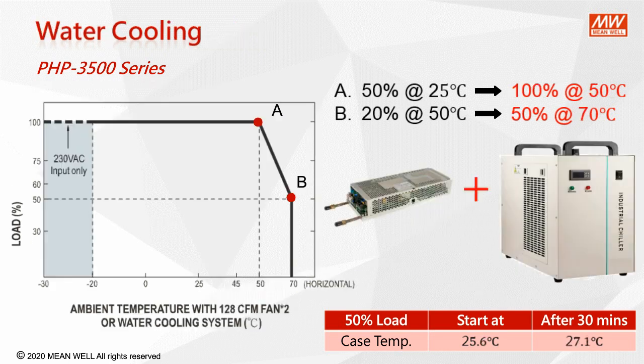Now, to access the full power output, we're looking at the water cooling performance curve. In comparison to the free air convection cooling curve, point A increases to 100% output power at 50 degrees Celsius, and point B increases to 50% at 70 degrees Celsius. After operating at room temperature for 30 minutes under the same load conditions as tested before, the same case temperature rises to 27.1 degrees Celsius, which is only 1.5 degrees temperature rise. This is a huge difference in comparison to the 15 degree Celsius rise in free air convection operation.